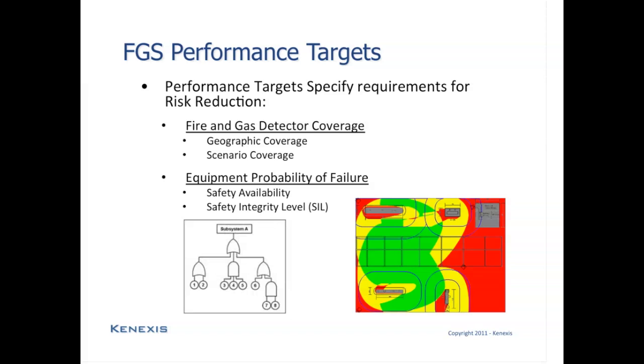Now, you'll notice that in our discussions of geographic coverage techniques, we didn't discuss at all where the fires or where the gas releases are likely to occur. All we looked at is essentially what the detector can see, and we completely ignored where the fires are coming from. In reality, we haven't ignored where the fires are coming from. We will address that issue a little bit later, and specifically, that issue is going to be covered by setting coverage areas and extent of covered areas when we use the semi-quantitative techniques. But when we're calculating scenario coverage, that's what we're going to consider: not only where the detectors are placed, but also where the risk scenarios are occurring.